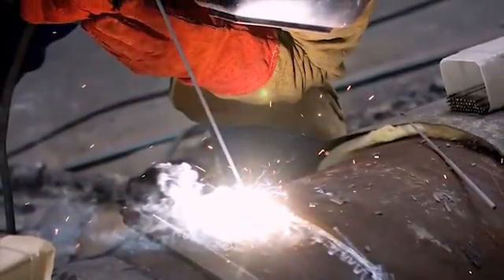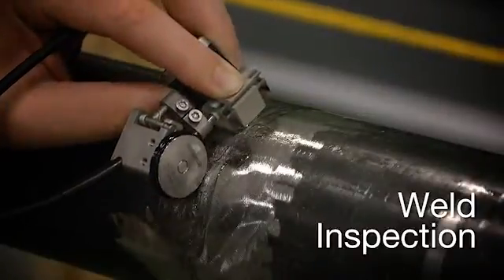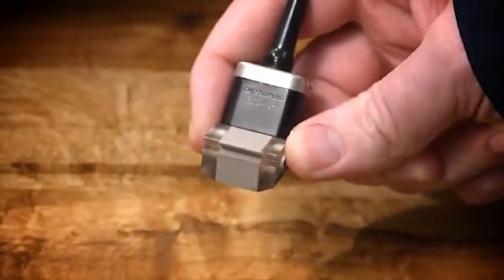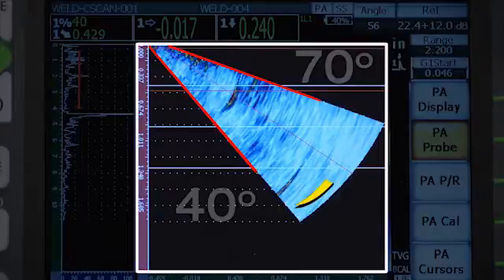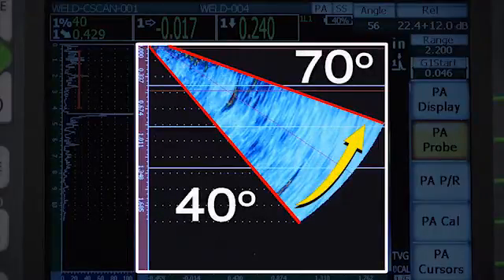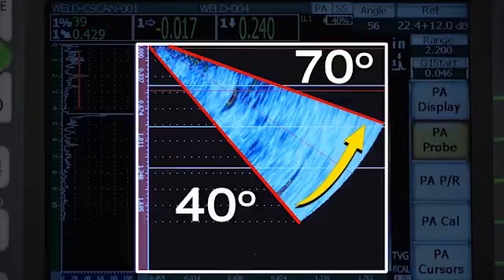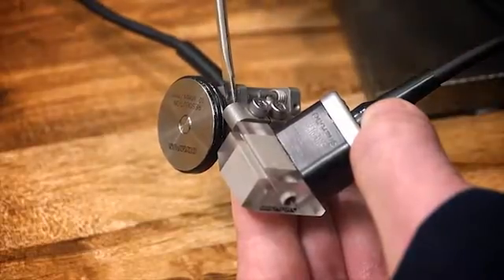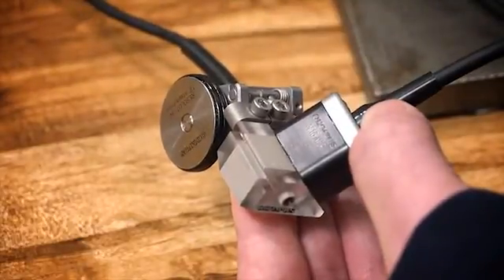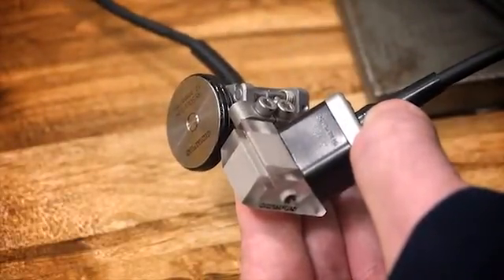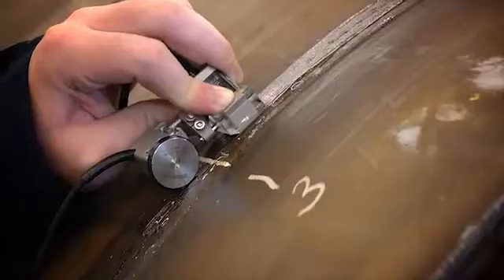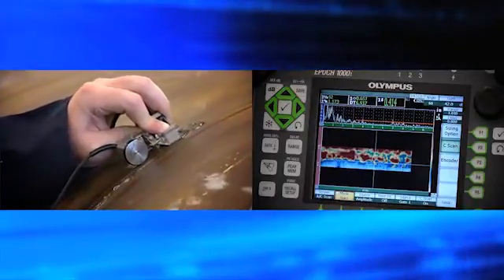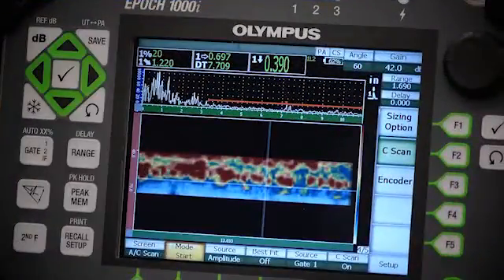One common usage of encoded C-SCAN imaging is in weld inspection. In this application, 8 or 16 element probes are used to create standard phased array sector scans. These scans provide you with information over a sweep of angles, usually 40 to 70 degrees, at a particular probe position. To create a C-SCAN image, these weld inspection probes are attached to a simple positional encoder. True depth gates are positioned to accumulate data within the desired leg of the weld. When you move the probe parallel to the weld axis, the gated amplitude data is plotted along the length of the weld at multiple angles, defined by the sector scan.